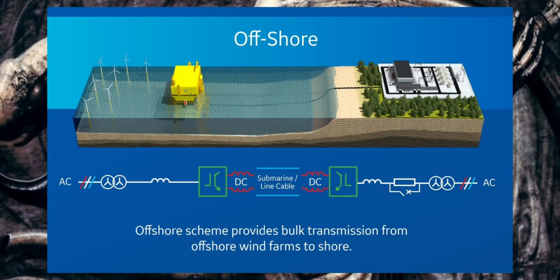Now consider offshore transmission of power generated by offshore wind farms to onshore facilities. The AC power generated by wind turbines is collected at an offshore substation, where it is converted from AC to DC for efficient long-distance transmission via submarine cables. At the receiving end, the power is converted back to AC for integration into the grid. HVDC transmission has become critical for the expansion of offshore wind as a power generation source.